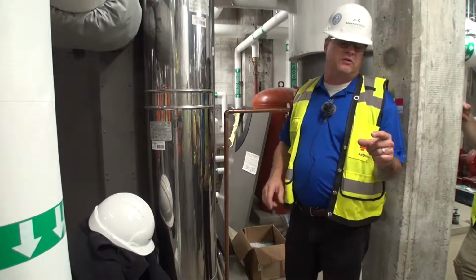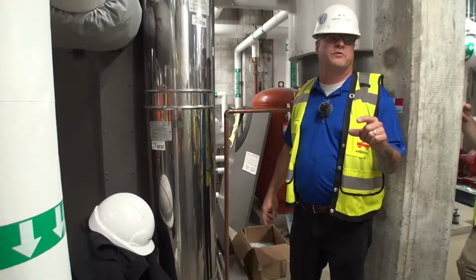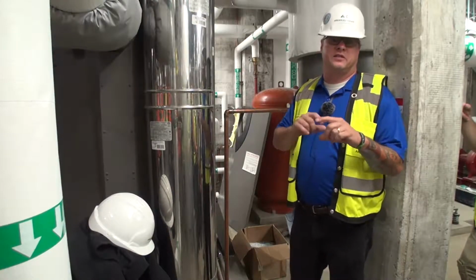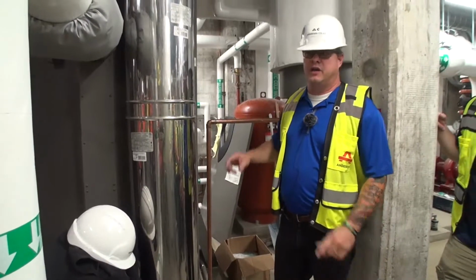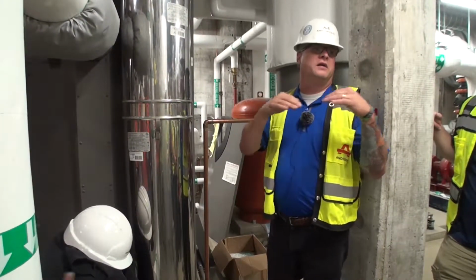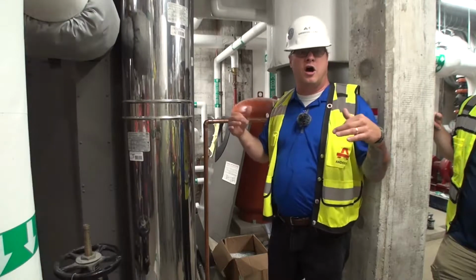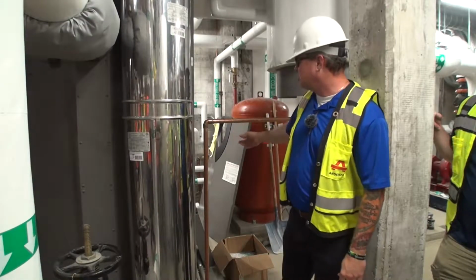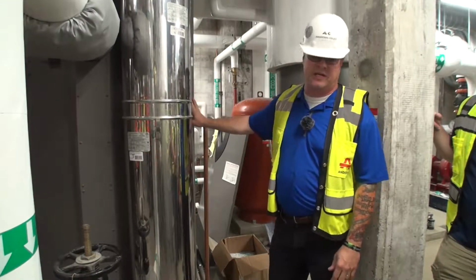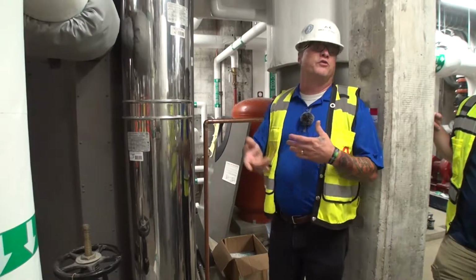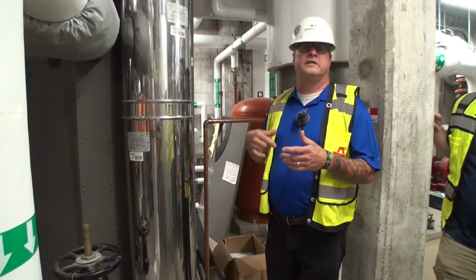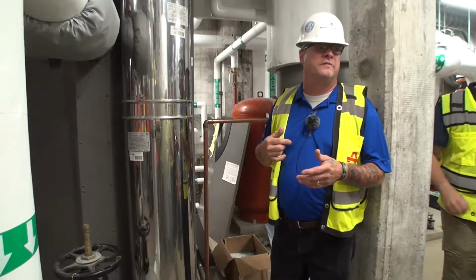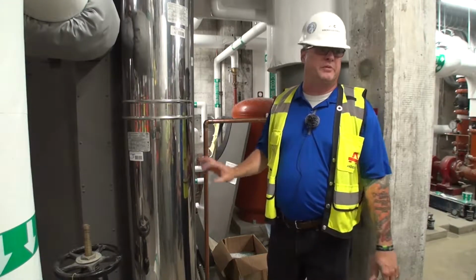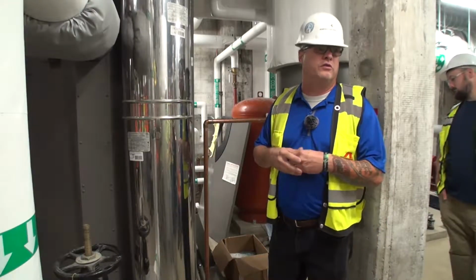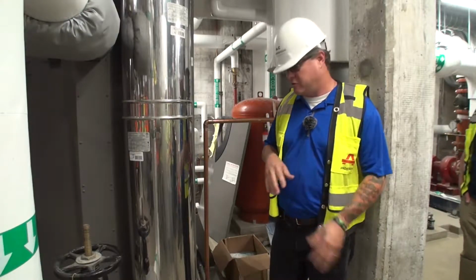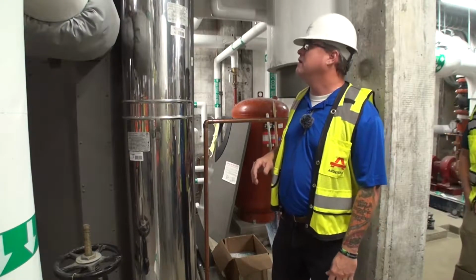Usually we use little paper strip testers for pH levels, and that's basically what you want to look at. It'll tell you if your media is being broken down and gone. Also, you want to make sure that when these are running and condensing, you do have flow through that, because if it doesn't flow, it starts to clog and then backs up into the vent, and then you might get fault codes in the sense of flue vent and everything else. So that's that.